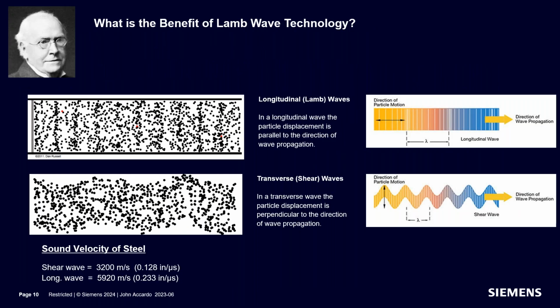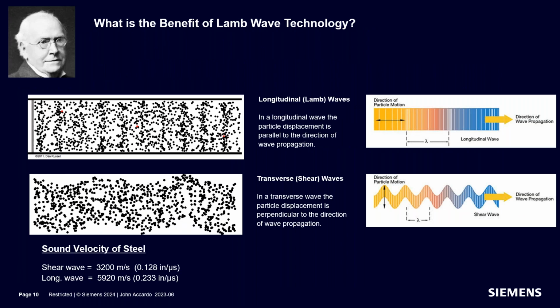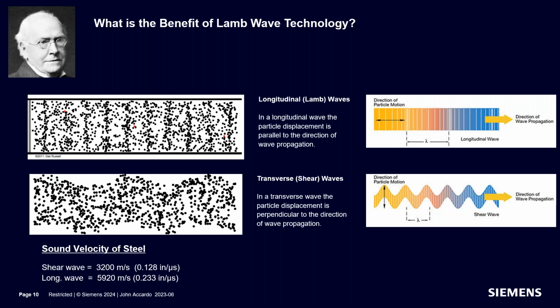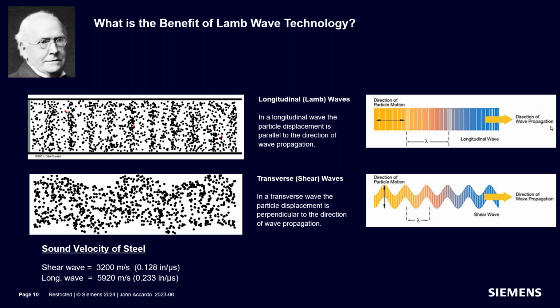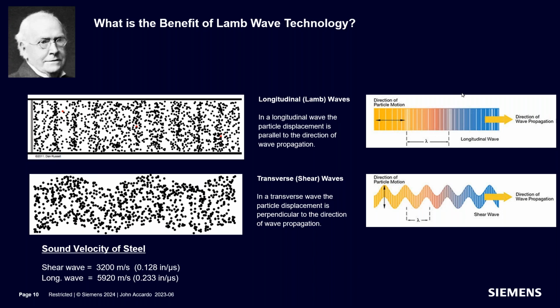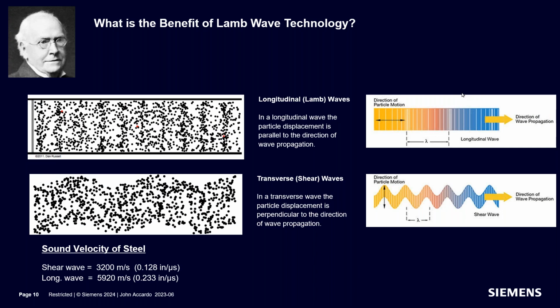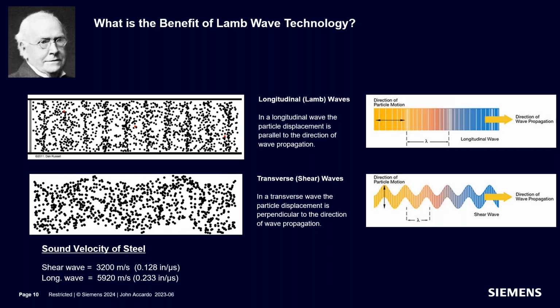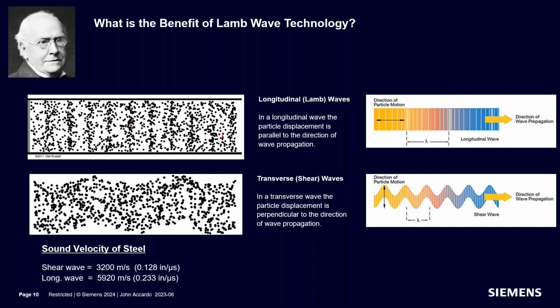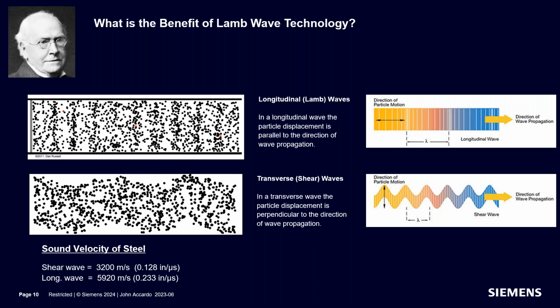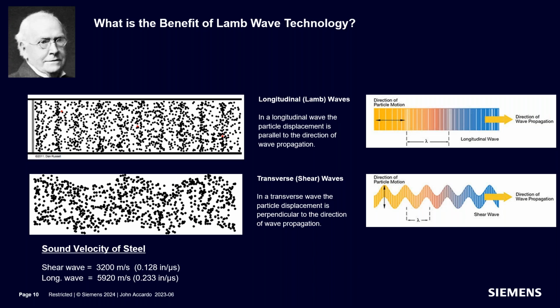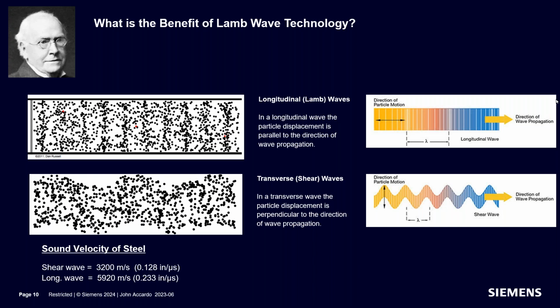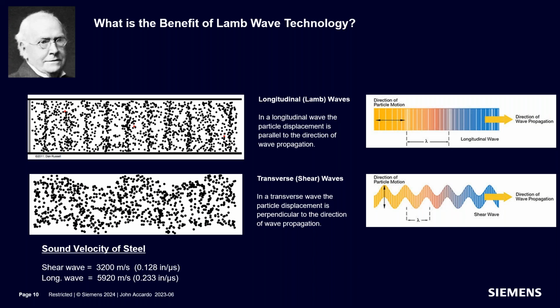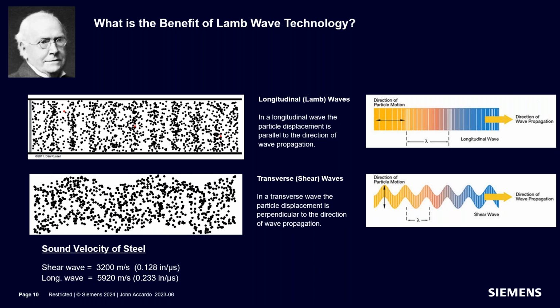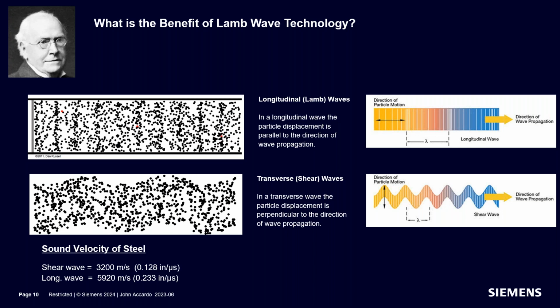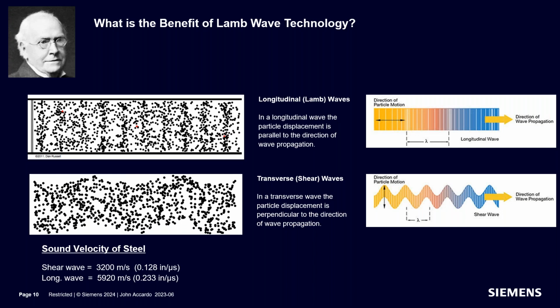So if we look at waves, what's the benefit of Lamb wave technology? If you look at the Lamb wave on top as a longitudinal wave, the beam gets injected into the pipe and it turns to 90 degrees. It turns to travel along the pipe and uses it as a waveguide. So it's traveling down the pipe wall, and it's literally like if you were to take a hammer and strike the end of the pipe. If you had the pipe square cut, you hit the end of the pipe with a hammer, it would push sound waves down along the pipe wall. And so the pipe signal will travel way down the wall, well past the receiving transducer, and just keep on going.